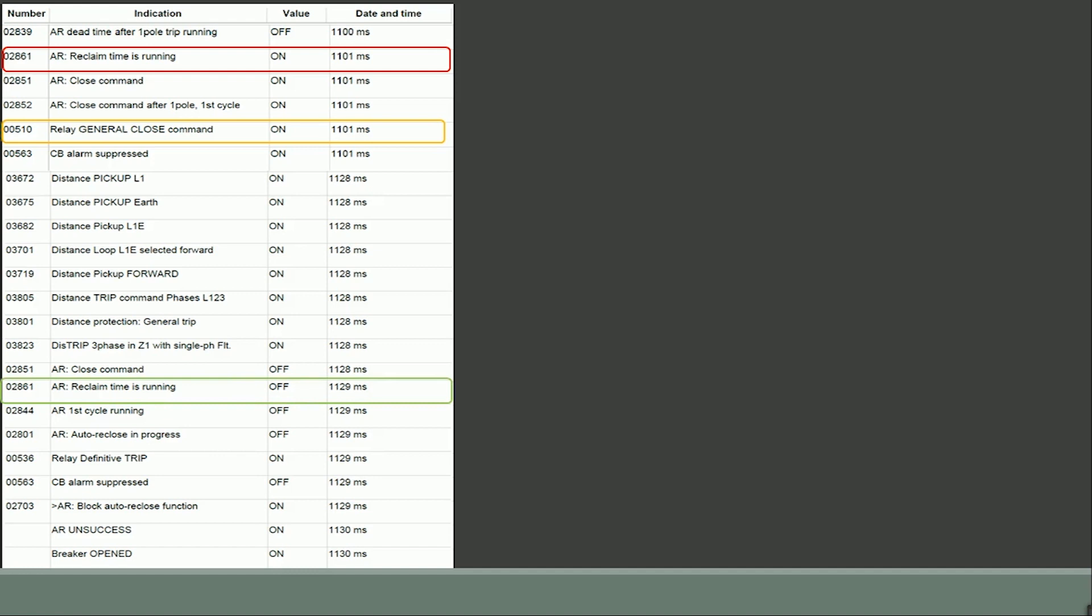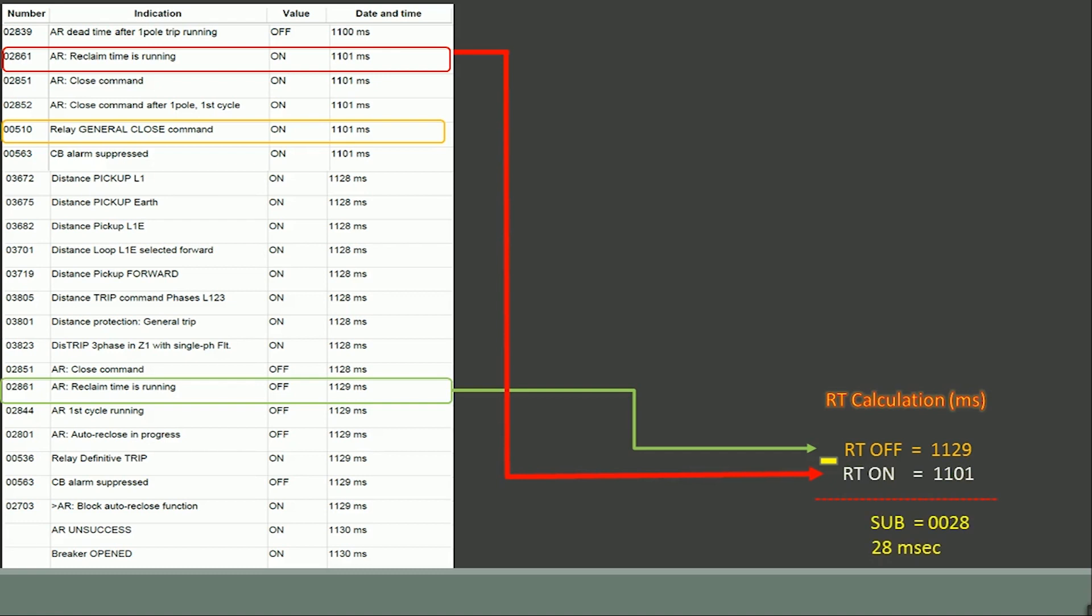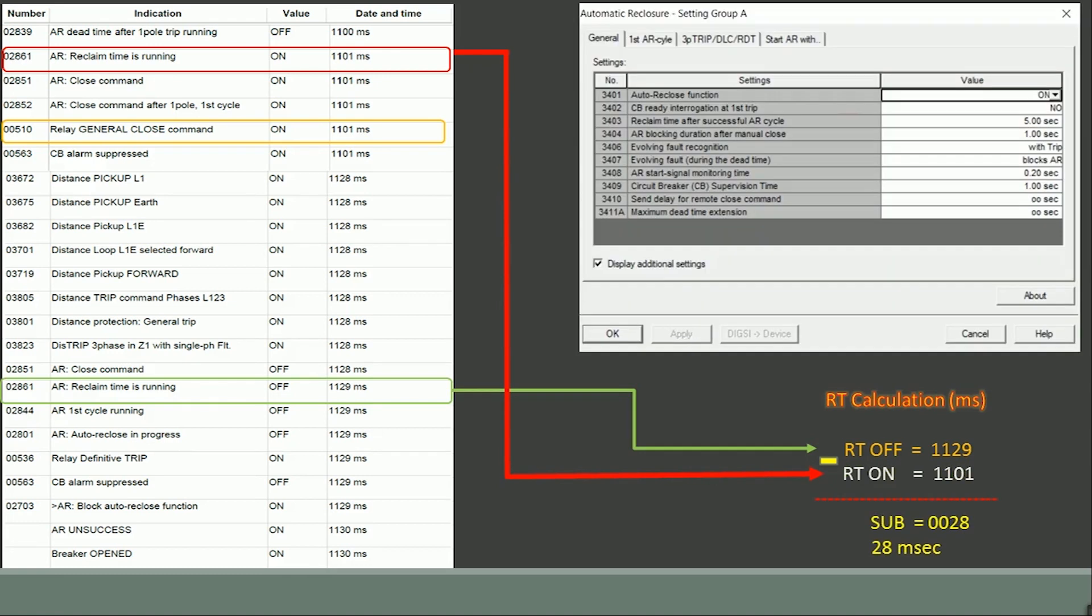The difference between reclaim off and on time provides the reclaim time configured in the relay as 28 milliseconds. This time is less than our actual set reclaim time of 5 seconds. Within this reclaim period another R phase to earth fault occurred in zone 1.